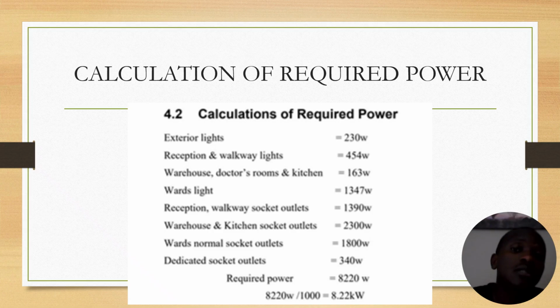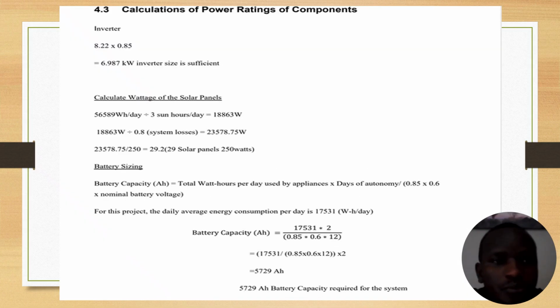8.22 kilowatts, this will be the power which is required for the whole hospital. This can ensure that there will be proper backup on the load. These are the calculations for power ratings of components, where for the inverter, I'm going to take the previous 8.22 kilowatts, then that 8.22 kilowatts will be multiplied by 0.85, then it will give us 6.987 kilowatts inverter size.